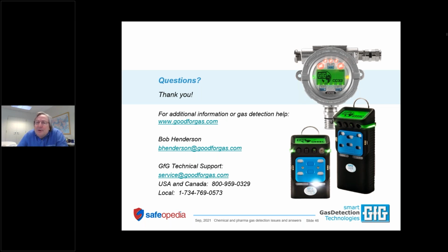Yes, you can, but let's say that you take my advice and you decided not to put the SO2 and NO2 sensor in the same instrument, even though you could. So I have NO2 today and I want to switch it over to SO2. Well, to do that, it's pretty easy. You take the housing apart, you access the sensor, you unplug one, you plug in the other, but you have to go through a warm up and calibration process before you can actually use the sensor.